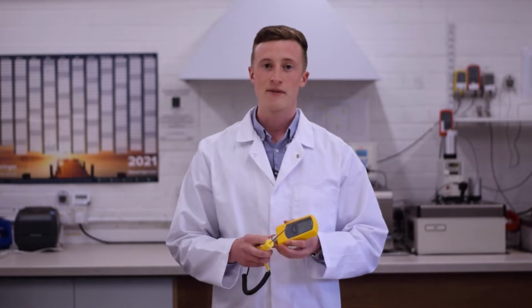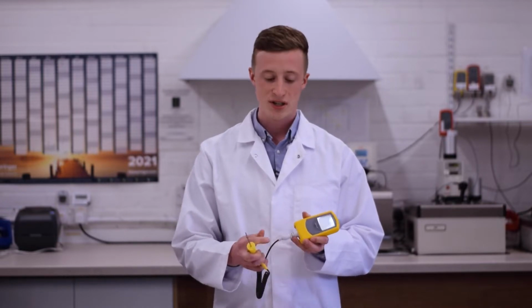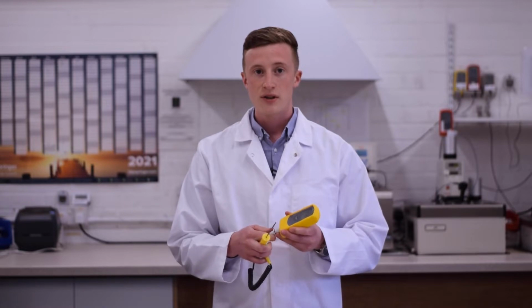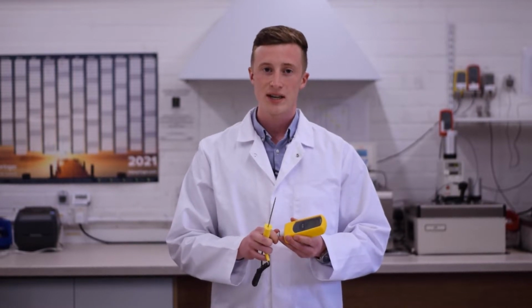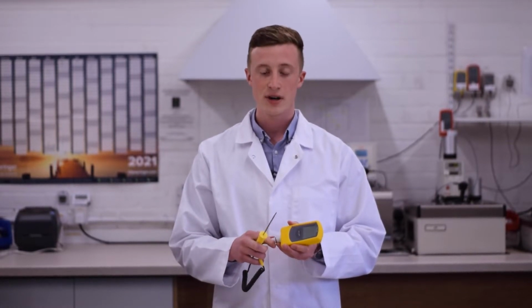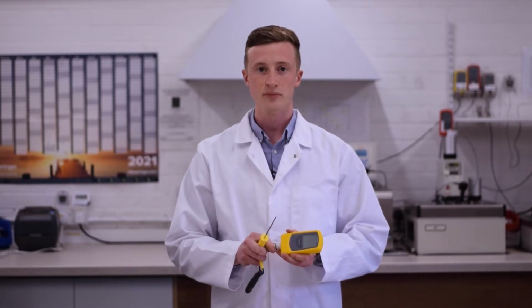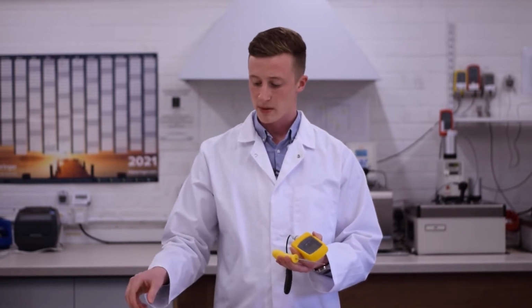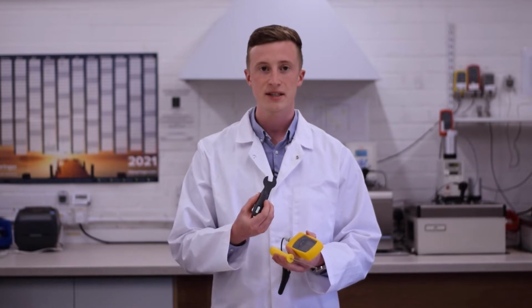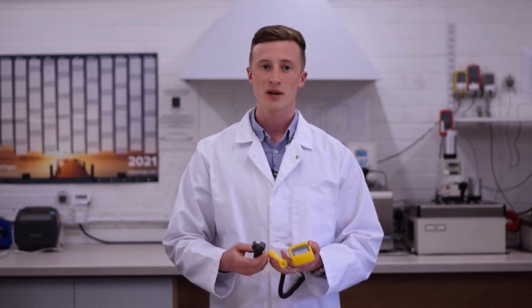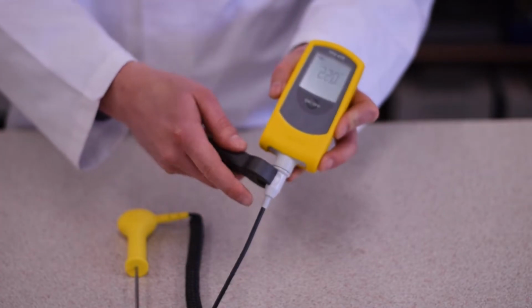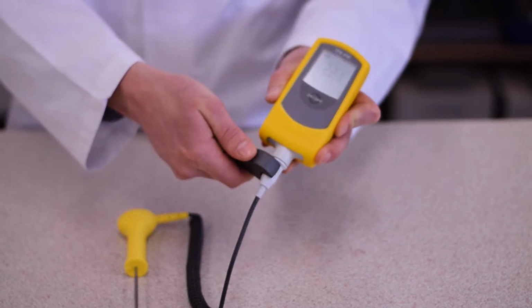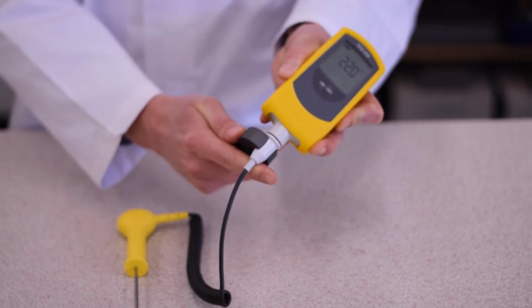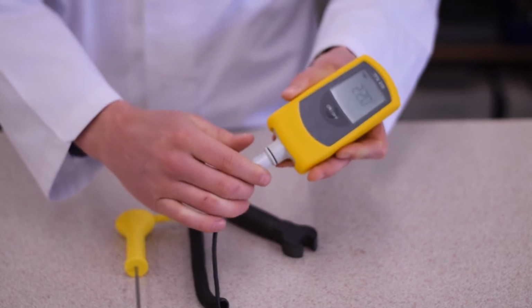It is, however, very important that you ensure this is correctly sealed so that absolutely no moisture can get in between the probe and the unit and penetrate the electronics. To change the probe, we recommend that you use the AEB60 cap change tool from Klipspringer. Firstly, twist the cap anti-clockwise 90 degrees to unscrew the cap.